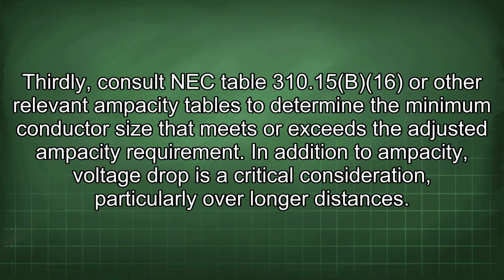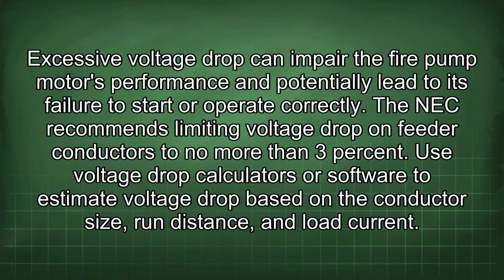In addition to ampacity, voltage drop is a critical consideration, particularly over longer distances. Excessive voltage drop can impair the fire pump motor's performance and potentially lead to its failure to start or operate correctly. The NEC recommends limiting voltage drop on feeder conductors to no more than 3%.